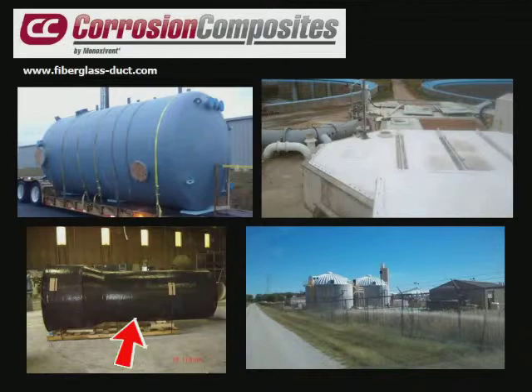The upper right-hand corner, we have some typical flat covers. And these are at the Cedar Rapids, Iowa wastewater plant. These have been in service about 5 years. They have another type of core, called a Nida-Core. It's a polypropylene honeycomb, and it covers all of the flat panels and makes it so that a man can walk on it, takes the 45-pound snow load, etc. Yet they stay lightweight and can be lifted off.